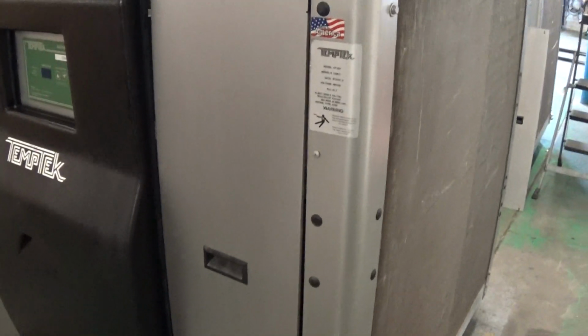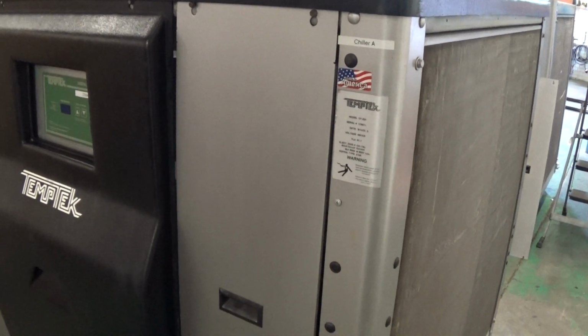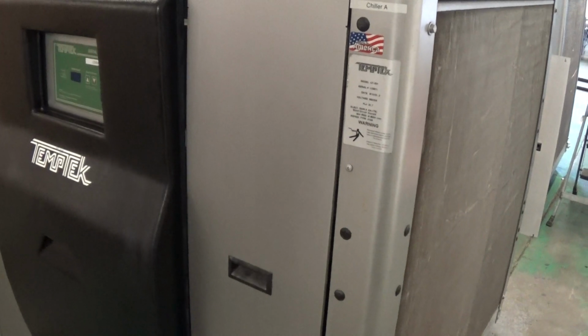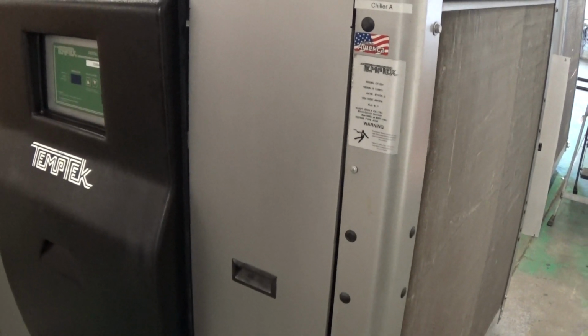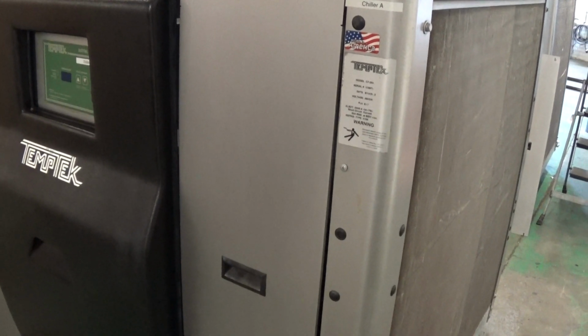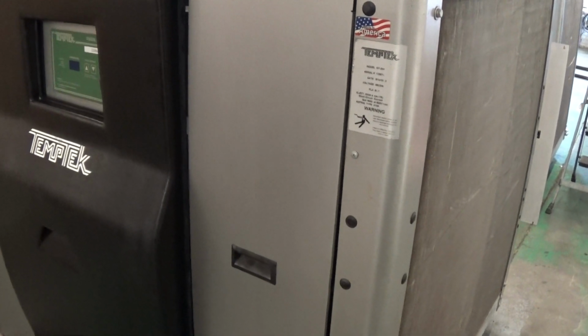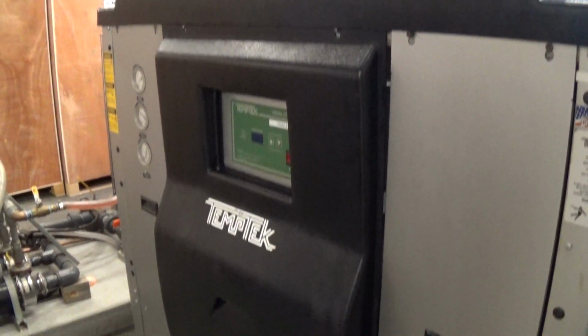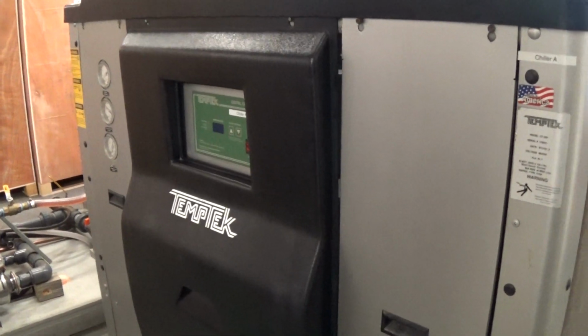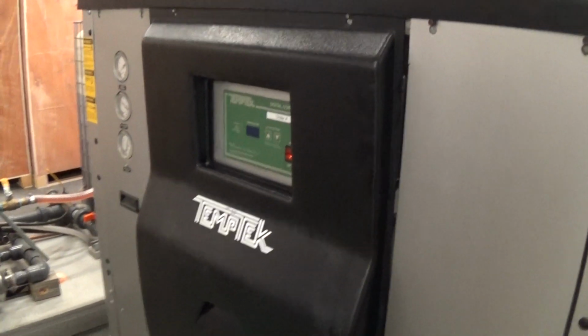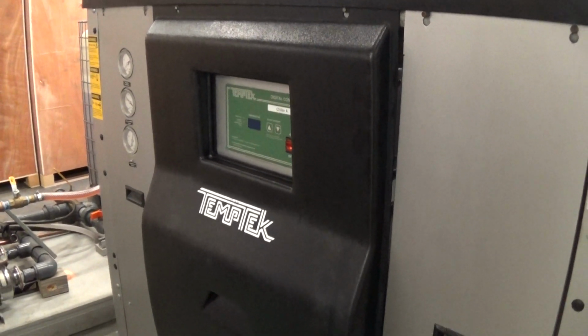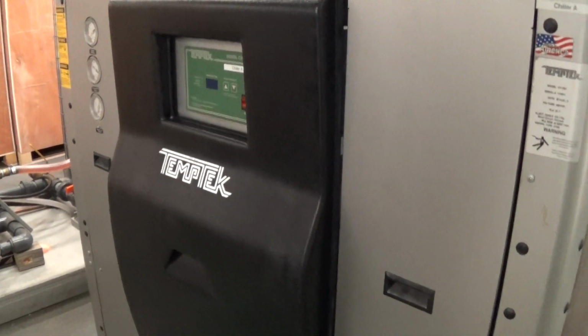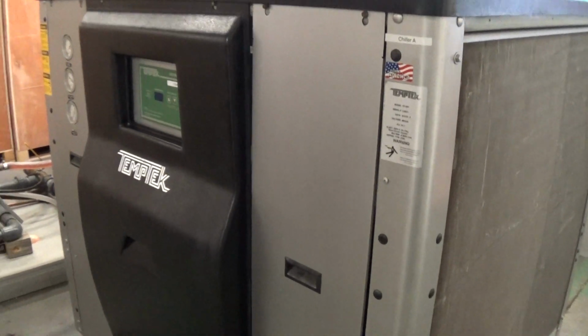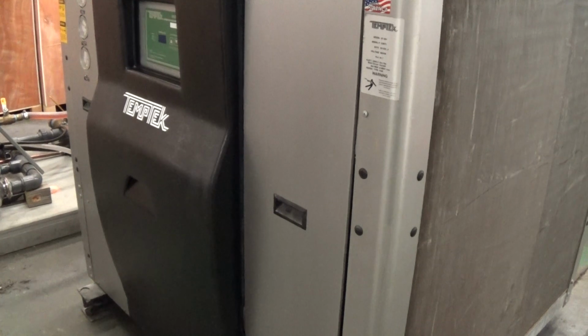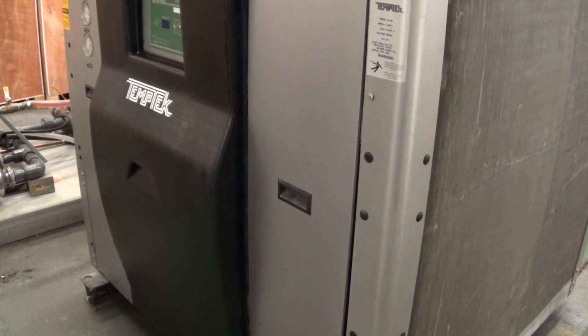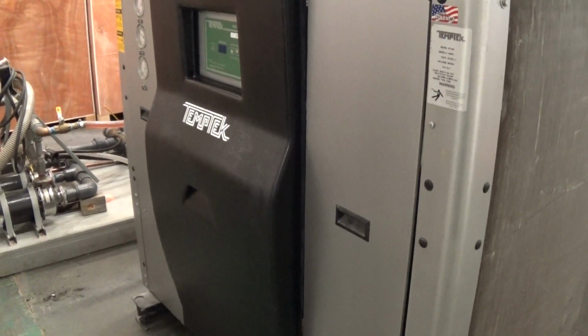Before we do that, worth mentioning or reminding, this is a 3-phase chiller, so the phase rotation is important. The easiest way to check that is when you first start the unit up. You can have this cover off here, and you can briefly turn the on button on while somebody's looking at the back of the pump to make sure the phase rotation is okay. Or, for that matter, the fan, because it is a 3-phase fan motor also. Make sure that's spinning in the right direction.